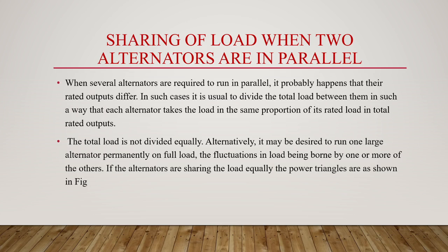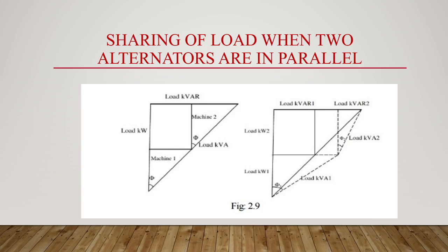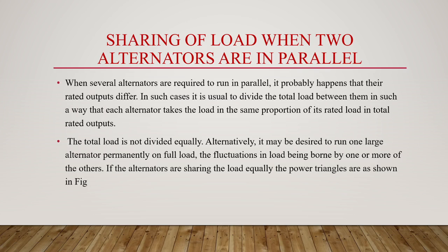If the alternators are sharing the load equally, then these are the power triangles. Okay, this is the power triangle where we can see on the y-axis the load in kilowatt, load in kVAR, kilovolt ampere reactive, and this is kVA. This is machine 1 and machine 2. And this is another phasor diagram showing load shared between two machines: load kilowatt 1, load kilowatt 2, load kVAR 1, load kVAR 2, load kVA 1, load kVA 2. So what we are saying here is that whenever we make several alternators run in parallel, their outputs may differ. So we divide the total load between them in such a way that each alternator takes the load in the same proportion of its rated load. It will adjust itself to the load and output.